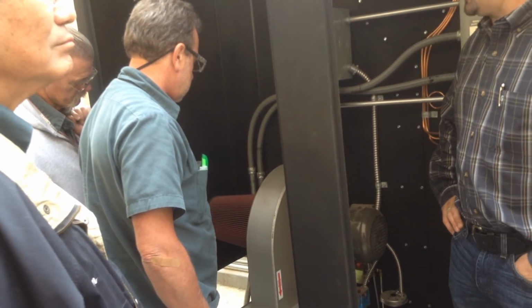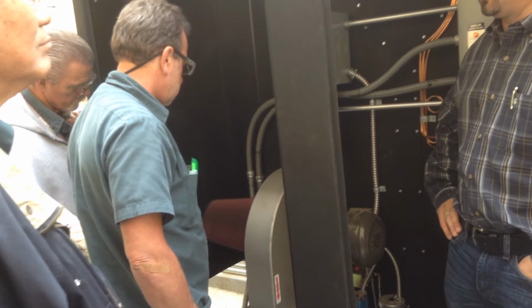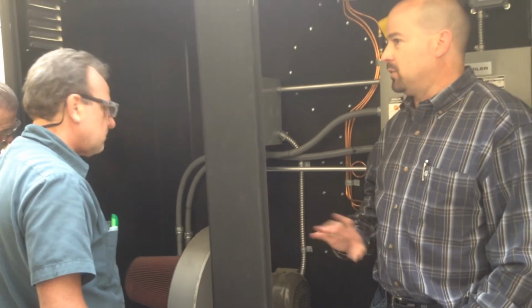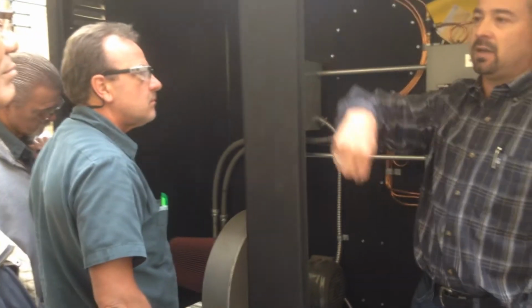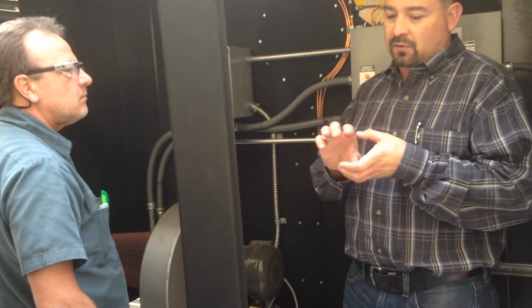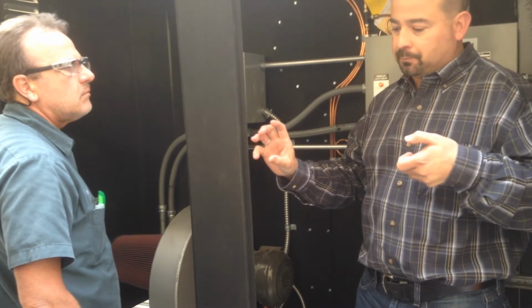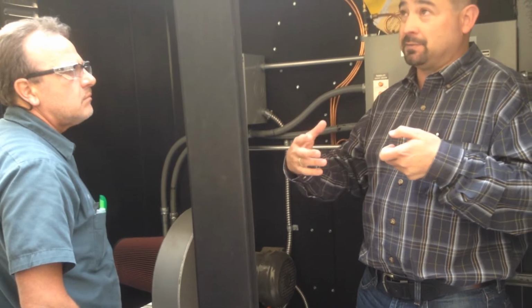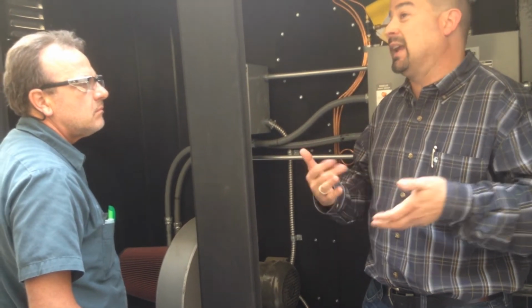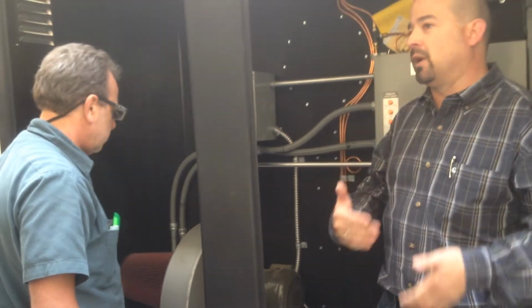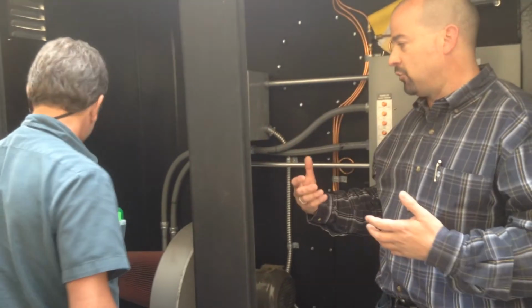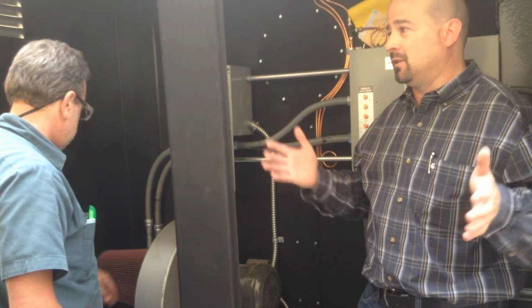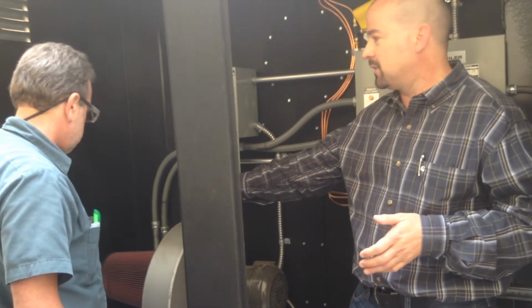Yeah. And I highly recommend, you can run it without the filter for maybe a day or something, but don't do it for longer than that, because then it'll get into the burners. And the burners are a metal fiber mesh burner. You probably have maybe 20, maybe 40 in there. There's a lot of burners in there. They're like $800 each. So you don't want to ruin them by getting them dirty. They'll last forever if that filter's there, you're fine.